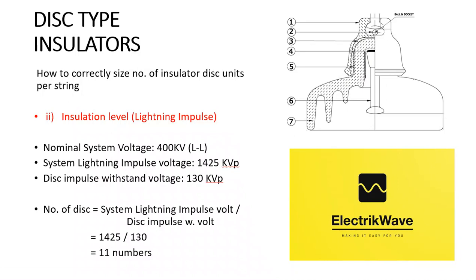Here we will calculate the number of insulator disk units per string based on insulation level. Nominal system voltage is 400 kV line to line. System lightning impulse voltage is 1425 kV peak. Disk impulse withstand voltage is 130 kV peak. The formula: number of disks per string = system lightning impulse voltage divided by disk impulse withstand voltage. This gives a requirement of 11 disks per string.